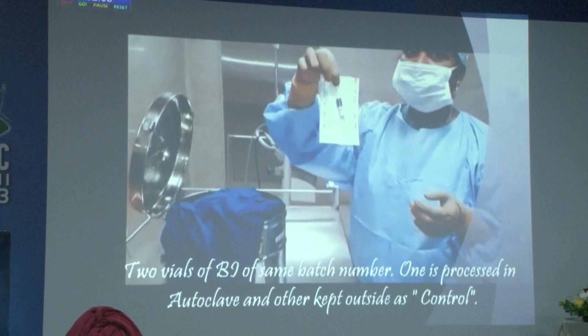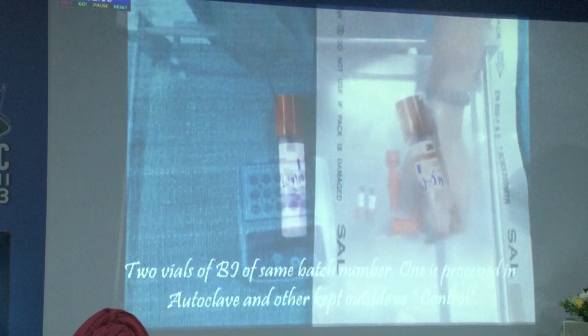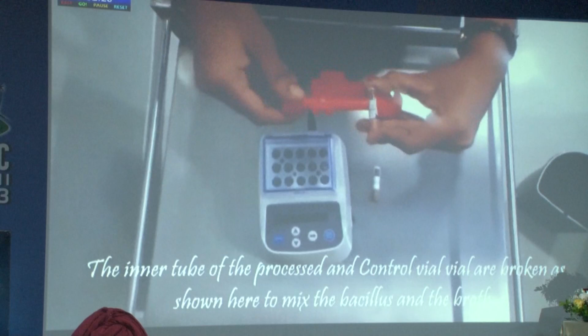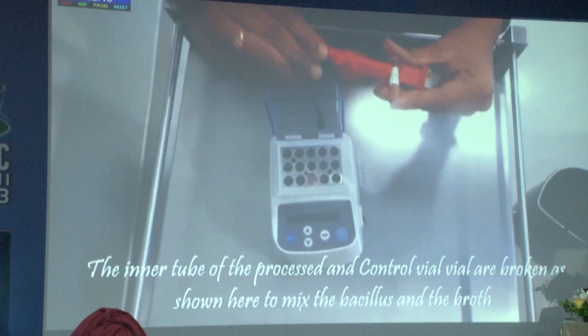You remove the processed vial, and you have to break the inner vial, which contains the broth and the indicator. Please place them only after breaking it, otherwise you would find all remains violet. So this makes the broth and the bacteria, which is Bacillus stearothermophilus, which is the most heat-resistant bacillus, incubated at 57 degrees Celsius for 2 days. Most of the time, you will read the result in 12 to 16 hours itself. The maximum has to be incubated for 48 hours.